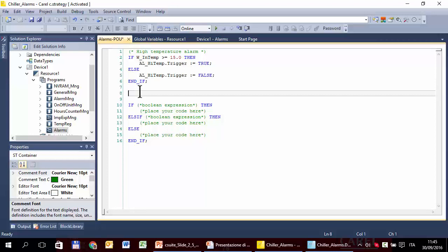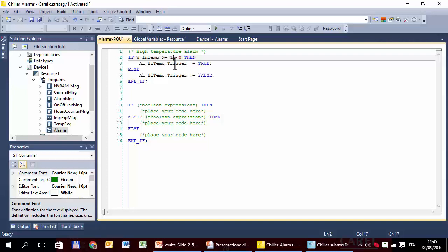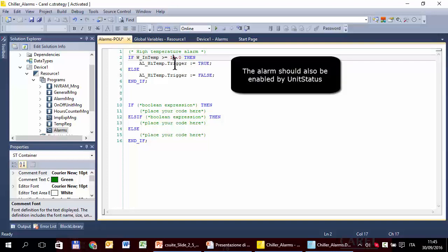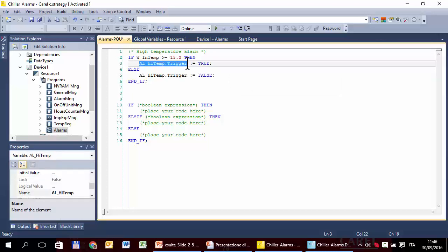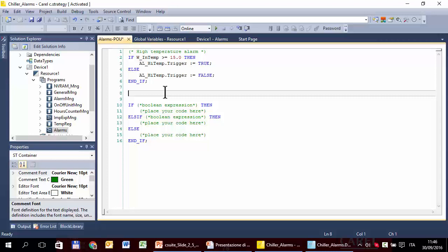What I'm doing here is a very simple alarm management — it is not real. A real application has at least a delay for the alarm, so it doesn't start immediately as soon as the temperature exceeds the limit. Or a differential — for example, starts at 15 and ends at one degree below. But this is an exercise. The key message is: the application has to manage the trigger. How the strategy manages the trigger and what logic is behind it doesn't matter — just manage the trigger.